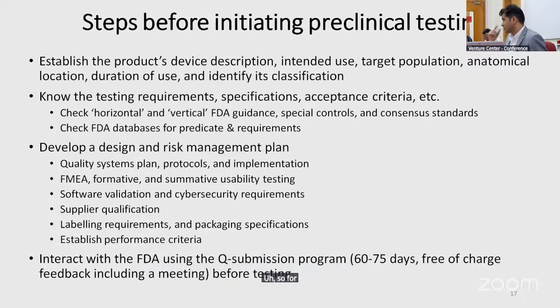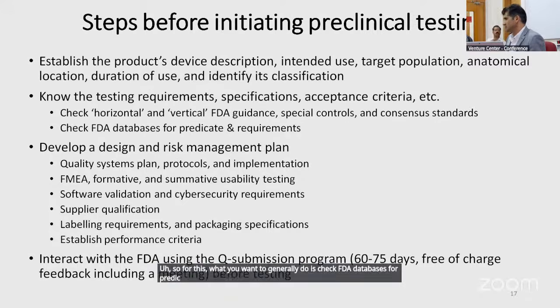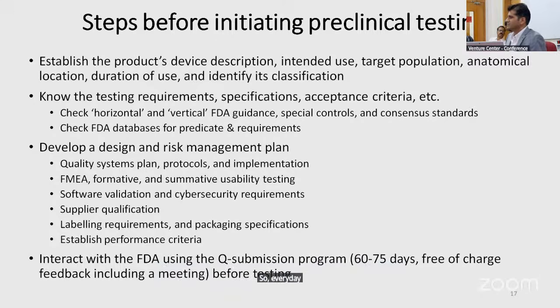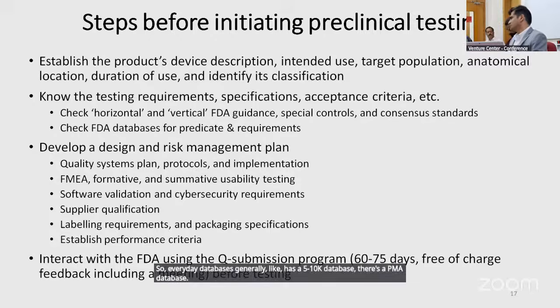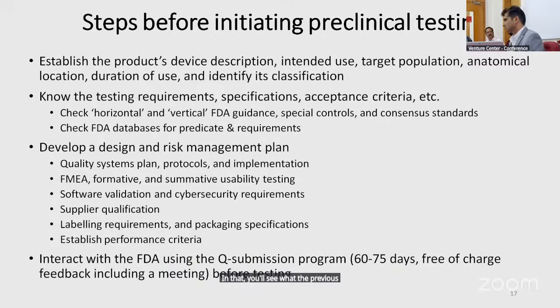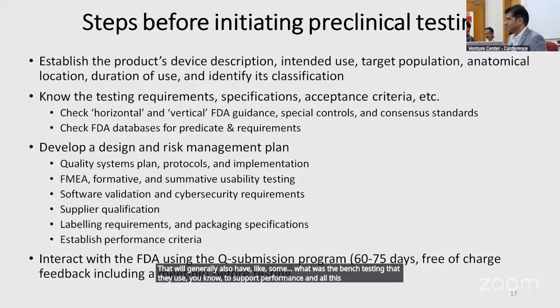For this, what you generally want to do is check FDA databases for predicates and requirements. FDA databases generally have a 510K database and a PMA database. In those, you'll see what the previous cleared devices are. And then you can look at the 510K summary. That will generally also have what bench testing they used to support performance, and will have some information on it. Only the summary is accessible, right? Yeah, not the full submission.